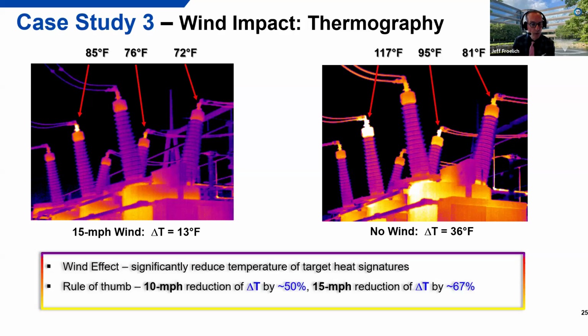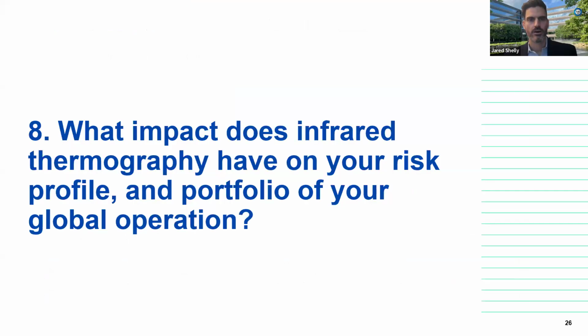And general rules of thumb, a 10-mile-an-hour wind gives a reduction of about 50% in the delta. That's the temperature rise I was mentioning, versus a 15-mile-an-hour wind, a reduction of potentially up to 67%. So it's a significant factor to be considered, because you might overlook something if you're just going straight in without a wind effect consideration. That's a great one, Jeff.